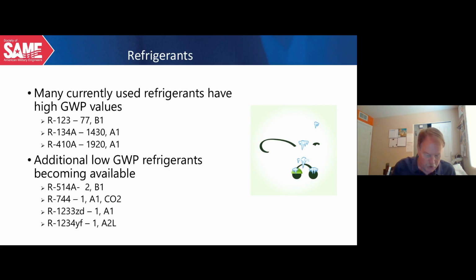Refrigerants. So as we see, refrigerants certainly are one of the emissions that leads to global warming. And what I've done is I've picked here a couple of our current refrigerants that have relatively high global warming values. Low pressure refrigerant R123 used in centrifugal chillers only has a global warming potential of 77, which is a relatively low number compared to the other two here. And it has an ASHRAE safety group classification of a B1 refrigerant.